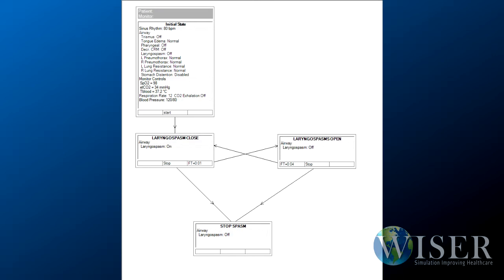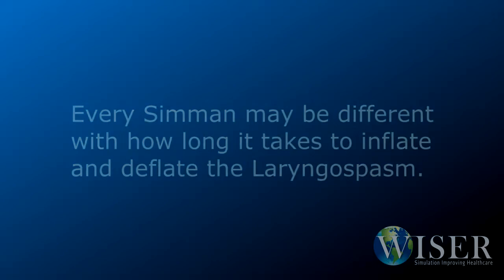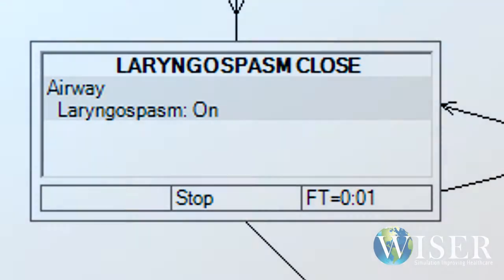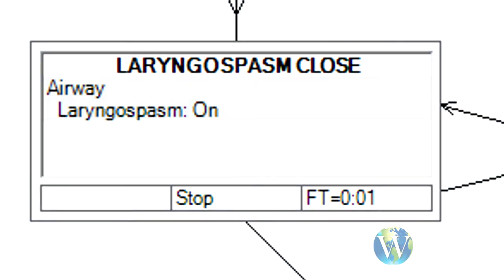The simplest loop would look like this. Every SIMMAN may be different with how long it takes to inflate and deflate the laryngospasm. The inflate time will normally be longer than the deflate time, so ensure that the frame that turns laryngospasm off has a slightly longer time before returning to the other frame.